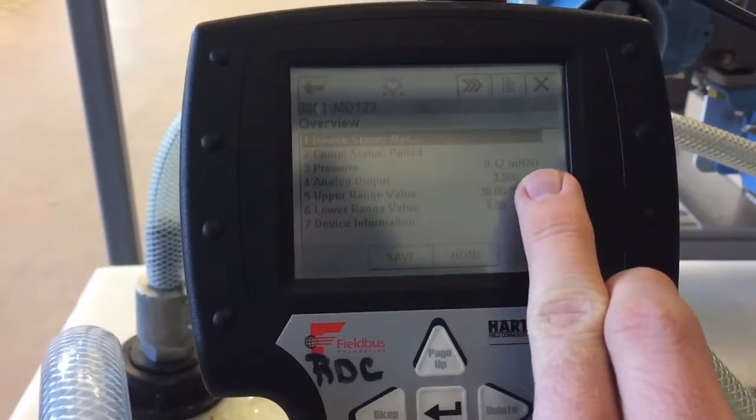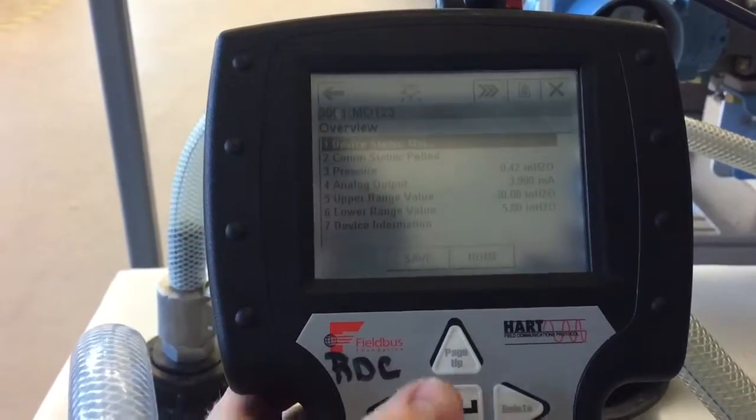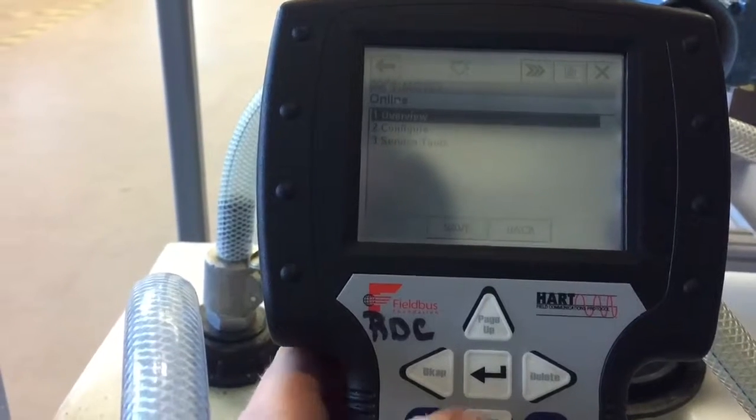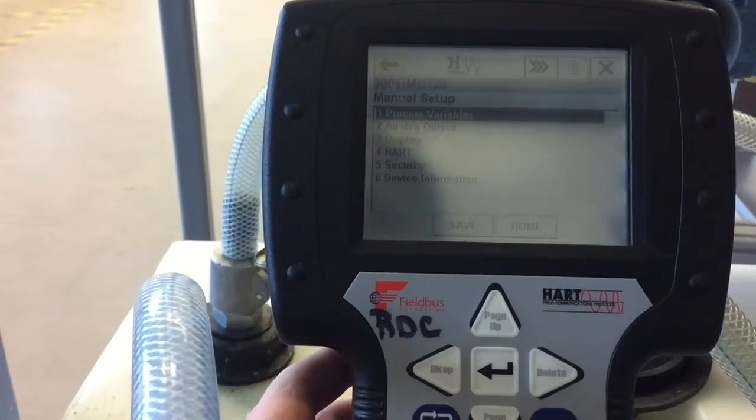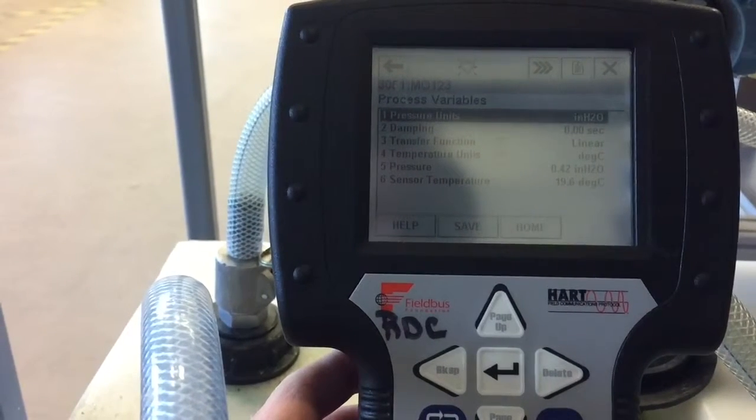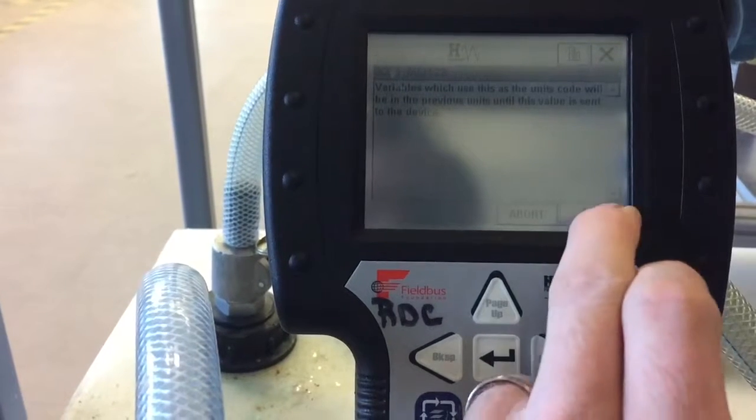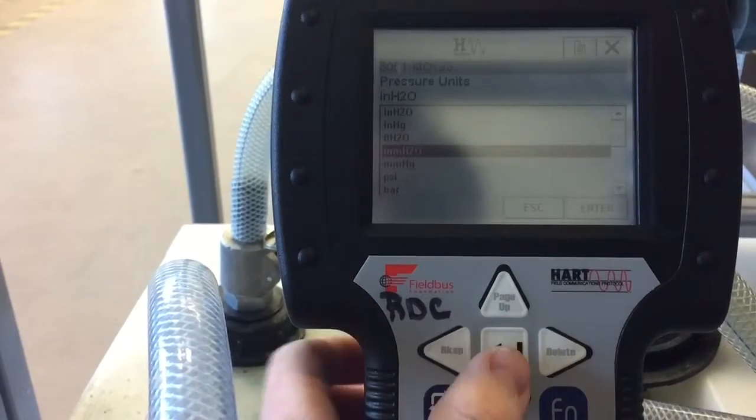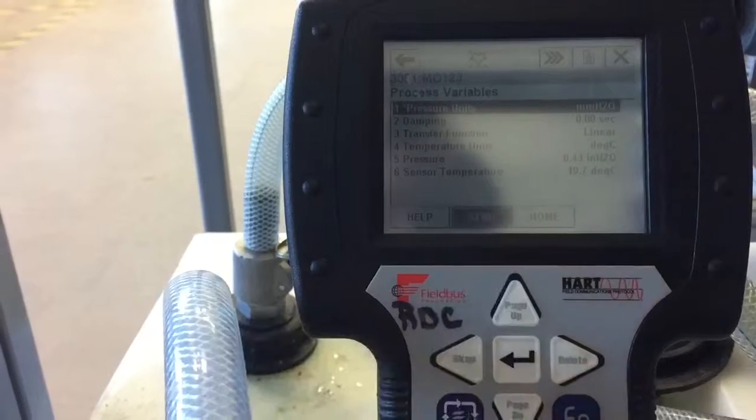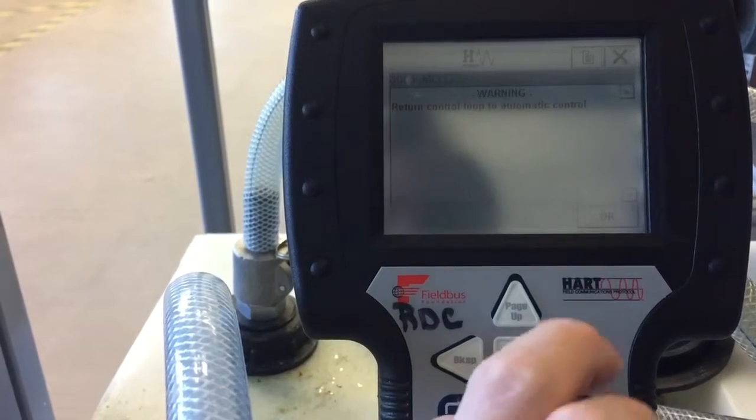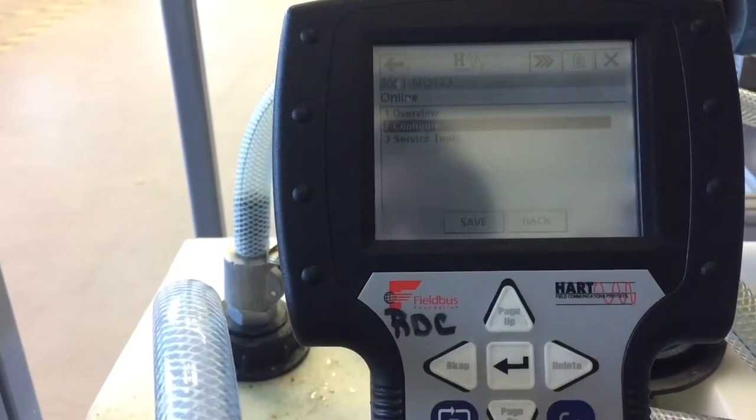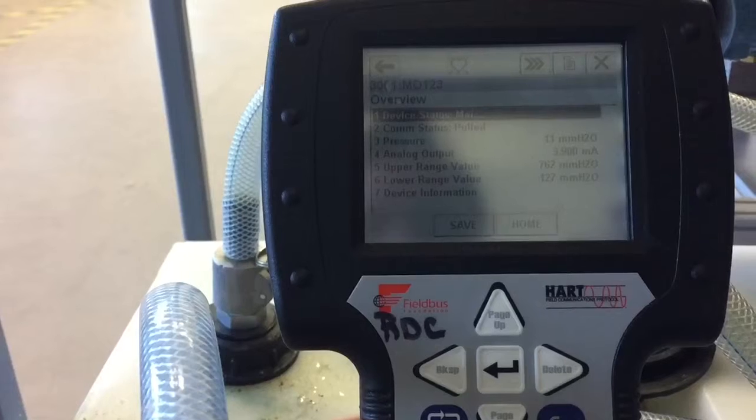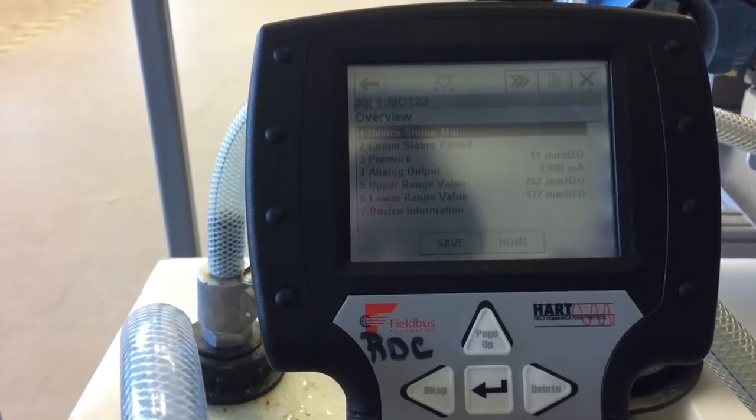Now we'll try switching the units back from the HART communicator and see if they update on the DeltaV control system. So I'll just have to go back to home here, configure, manual setup, process variables. Let's change the units now back to millimeters H2O. Enter, send. Okay, so it looks like it's updated here in the HART communicator. Let's just go back to our main overview. There, back to millimeters H2O. It automatically rearranged for us, updated the values.